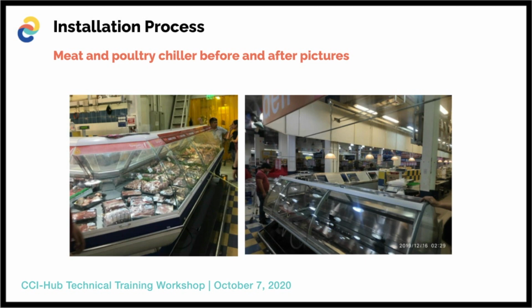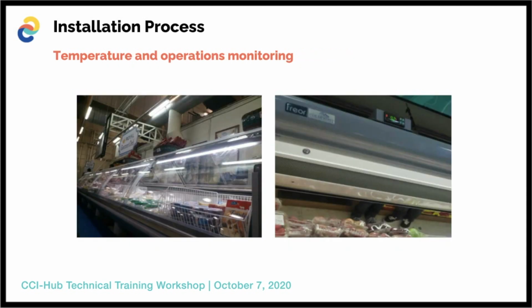Temperature and operations monitoring. Before the morning opening of the store, we need to set the R290 showcase into the respective temperature range. As per experience, the average time needed for the showcase to reach the design temperature using the R290 system took only 1 to 2 hours, whereas the R404 system may take 3 to 4 hours. Since the showcase is loaded with products right after the testing, a monitoring personnel was on standby to check the overall operation and functionality of the system.